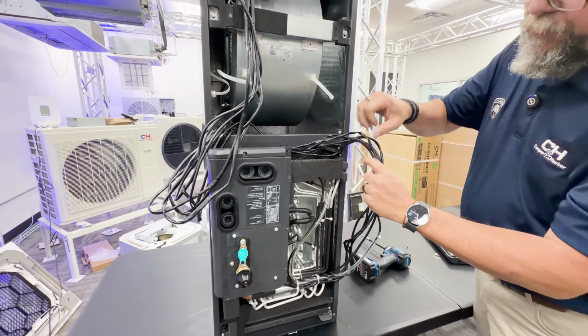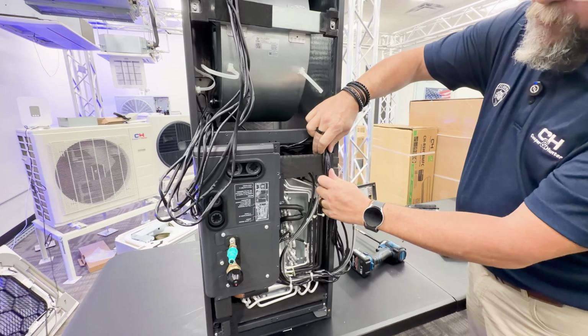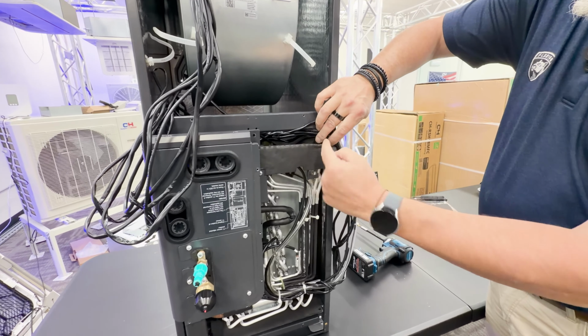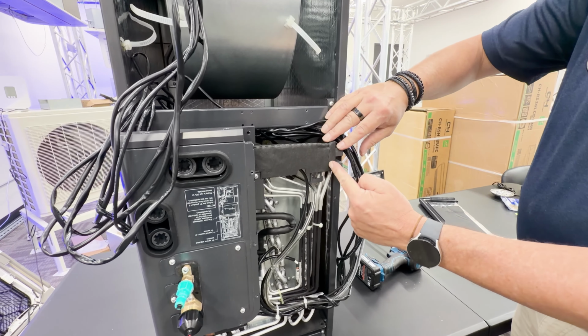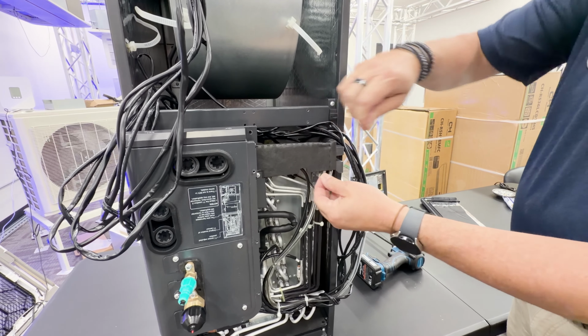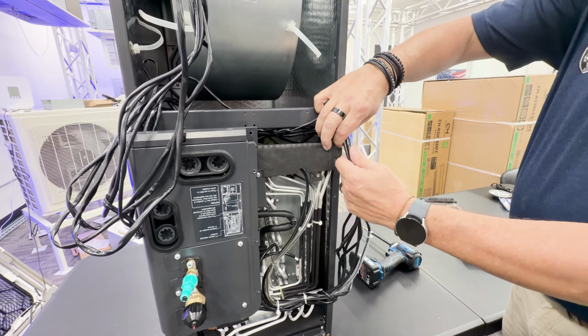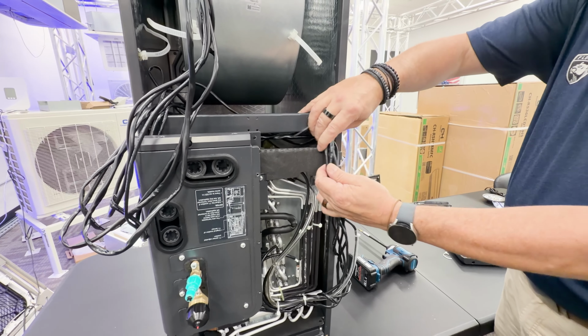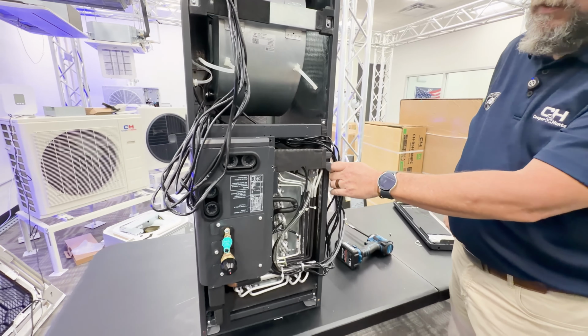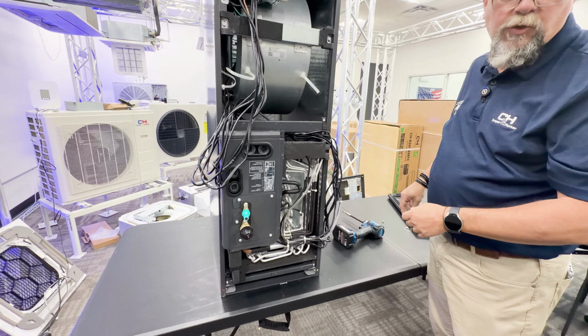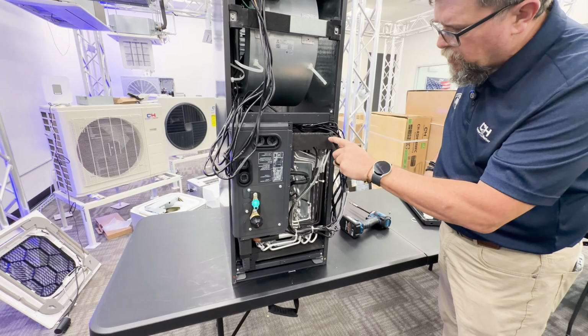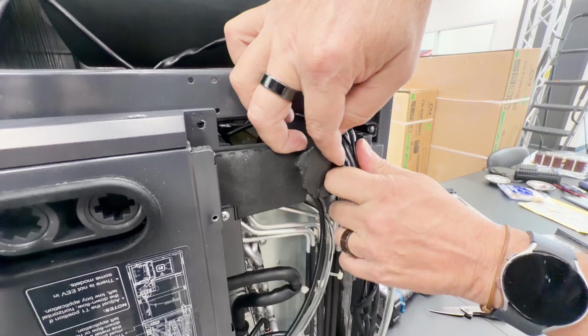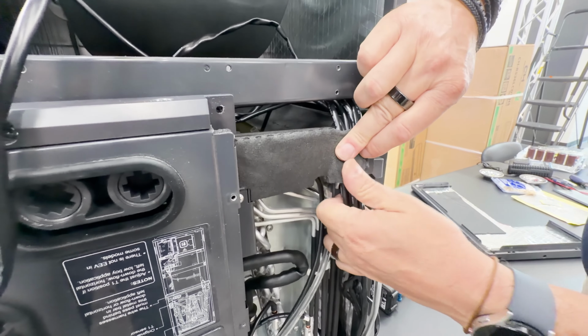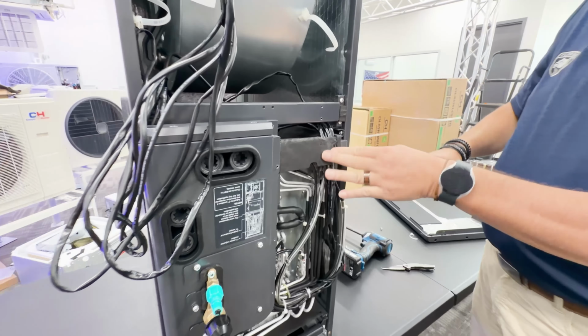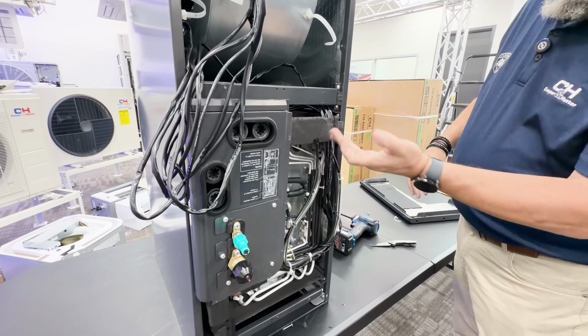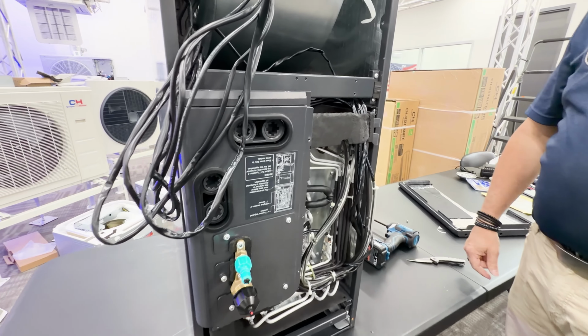With the coil back in place, one of the things we need to do to help with routing the wires is you'll see there's a little perforation here. You can cut that perforation and fold this back, put the wires underneath, and then flip it back so it stays insulated with less chance of condensation dripping somewhere it shouldn't. There's a little trough here for the wires, so it's not on any sharp edges. It's sticky back, so you can push it over and the wires are protected.